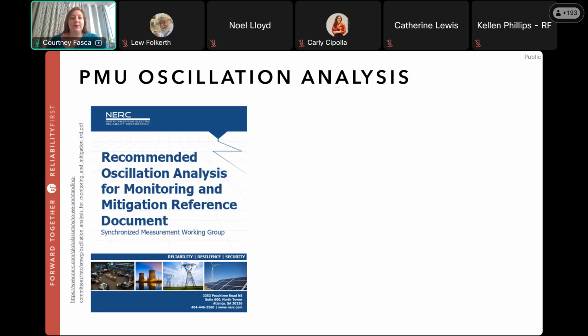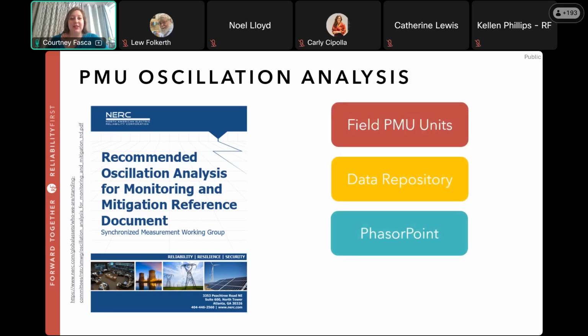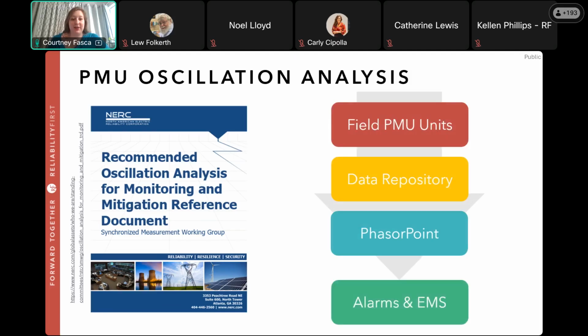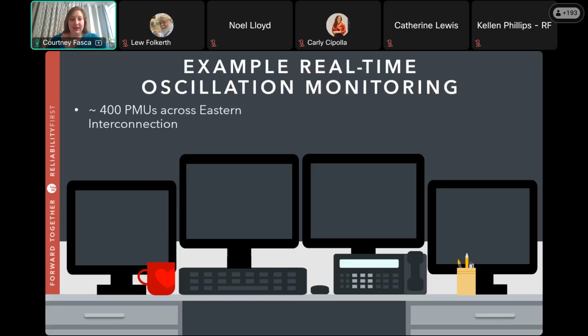So they have field PMU units stream high sampling data to a data repository, and that data repository system will then dispatch PMU data streams to PhasorPoint, in which real-time monitoring is enabled, and alarms are generated and transmitted to the EMS. So as of the release of this paper, the utility deployed close to 400 PMUs across the Eastern interconnection. So with that large amount of data accumulated, real-time oscillation event detection on frequency and active power was developed and deployed in control rooms to enhance situational awareness.